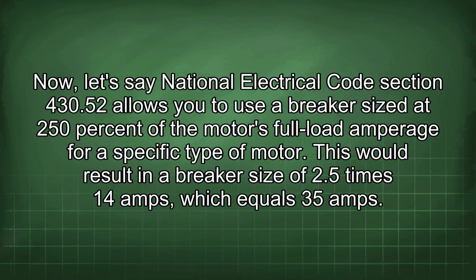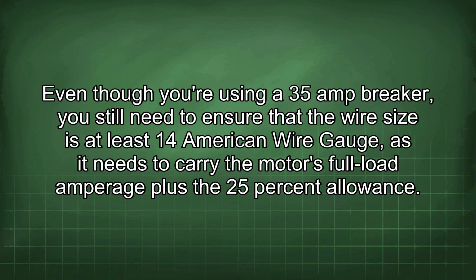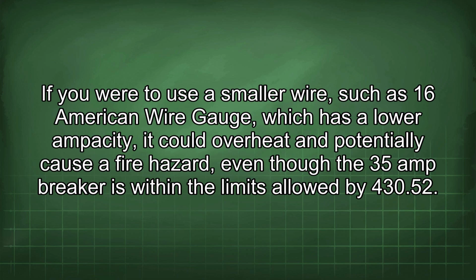Now, let's say National Electrical Code Section 430.52 allows you to use a breaker size of 250% of the motor's full load amperage for a specific type of motor. This would result in a breaker size of 2.5 times 14 amps, which equals 35 amps. Even though you're using a 35 amp breaker, you still need to ensure that the wire size is at least 14 American wire gauge, as it needs to carry the motor's full load amperage plus the 25% allowance. If you were to use a smaller wire, such as 16 American wire gauge, which has a lower ampacity, it could overheat and potentially cause a fire hazard, even though the 35 amp breaker is within the limits allowed by 430.52.